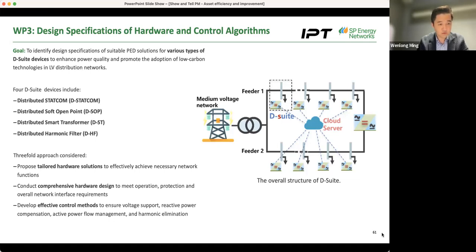The other thing we've done is the hardware design on that module - designing the parameters, for example what switches, capacitors, and inductors we're using, how to optimize them, and how to protect them under grid fault, also considering internal fault or over-voltage and over-current. Lastly, once we had that hardware, we developed some control methods. Again, it's modular, with different layers from the bottommost switch layer control up to the system layer control and interaction with the system.